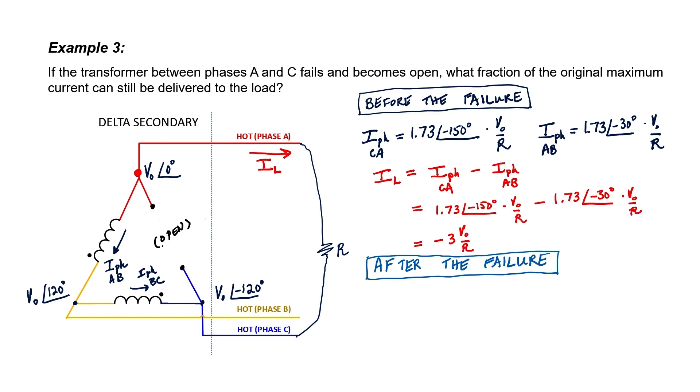the currents are going to change just a little bit. The phase current between A and B is going to be just what it was before because the voltage between phase A and phase B is exactly what it was before the failure. This current is going to be zero because it's not flowing at all, and that's going to cause the line current to change.